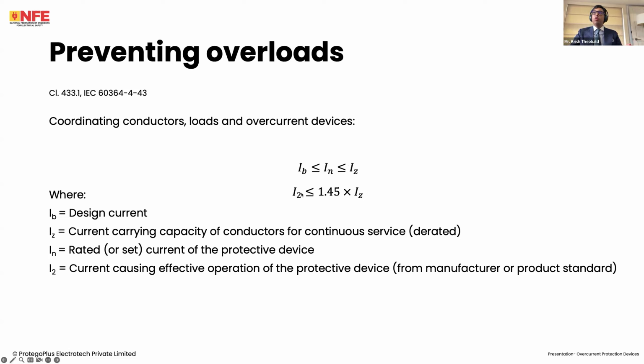Now, I2 is another interesting value. If we have, say, a 10 amp device or a 100 amp device for that matter, once the current reaches that value, whatever the rating of the device, IN, the device is not immediately going to trip. In fact, if it's 100 amps and you have 110 amps flowing through, it's unlikely to trip at all. These devices are designed with something called a conventional tripping current, or a conventional current causing effective operation, and these values are rated in multiples of IN.